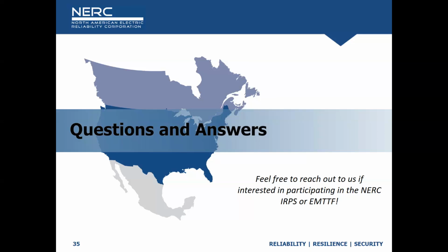That sounds good. Yep. So it sounds like really there's two issues, right? One issue is the IBRs aren't performing their ride-through capabilities the way that was expected. And the second issue is that what was expected wasn't what was going on, right? What was modeled and what was studied, both before and after one of these disturbances, wasn't matching the performance of the actual site. Does that sound like a good summary? All right, three nods, I think. I can't see Josh. I'm just going to assume Josh nodded. Yeah, thumbs up is good.